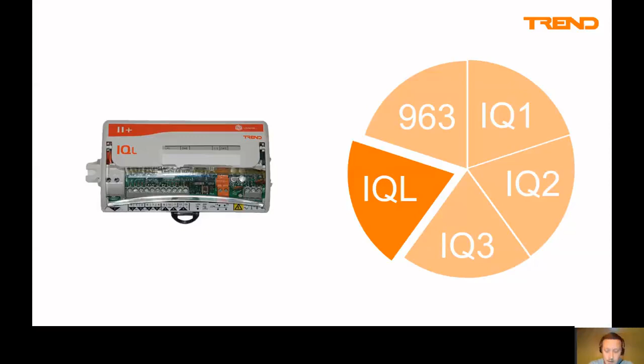Finally, you have 963, the graphical front end for trend, again now obsolete. This isn't just about controls, it's also PCs and operating systems. As of January 2020, Windows Server 2008 and Windows 7 are no longer supported. Windows CE, which a lot of OEM products still use, will no longer be supported from April 21st. From our perspective, operating systems less than Windows 10 are probably not going to be supported. So when thinking about obsolescence and upgrading the control system, you also have to think about the operating system, because if a PC fails and you're still running an old system that can't be replaced, you need to upgrade your front end too.